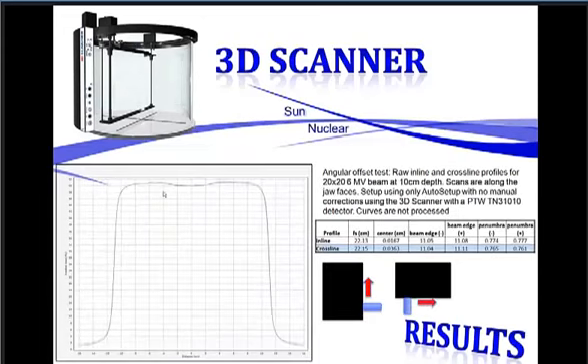One of the things we like to check as far as our consistency of setup and also how well we accepted the machine is we do what we call jaw face scans. It tests the angular offset. How well did the auto setup routine adjust the angular dependence to the skew of the jaws? So we went in and we actually scanned. We bring the jaw all the way into central axis and then offset it. So you're basically scanning at the 50% line. You can see from the graph there on the left we're basically right at the 50% line. Then we scanned a 20 by 20 and we scanned right along that jaw face. So you're looking at the skew of your jaws and how well you did during acceptance and beating up on your service engineer or your installer to make those things nice and straight.